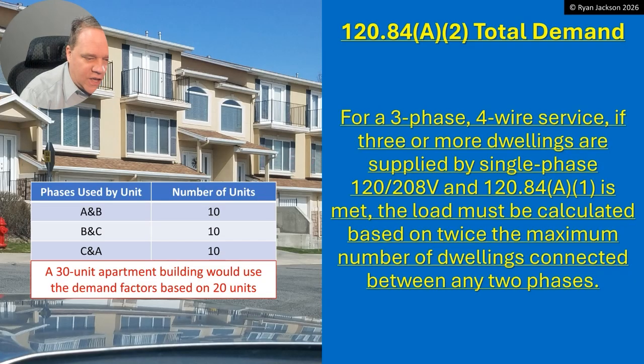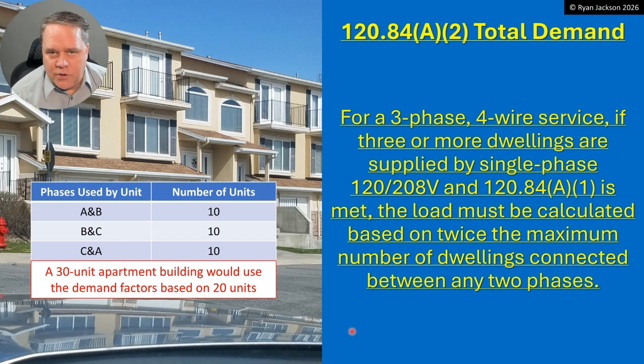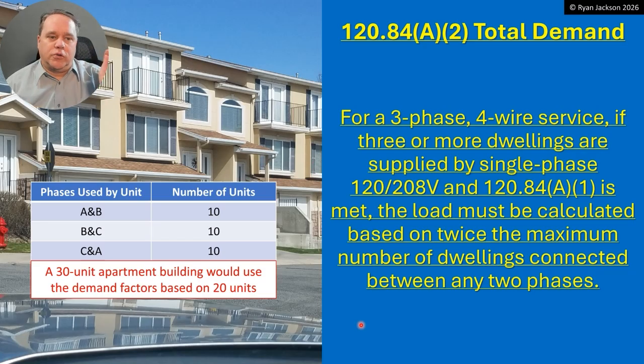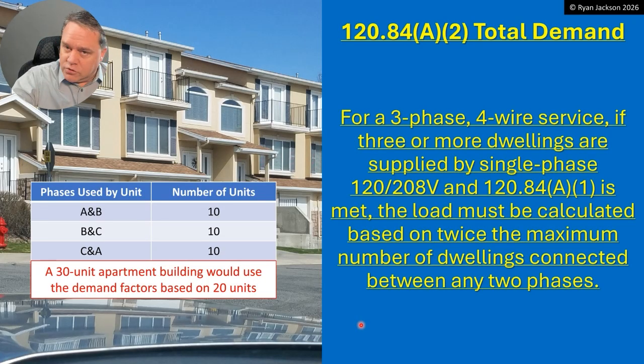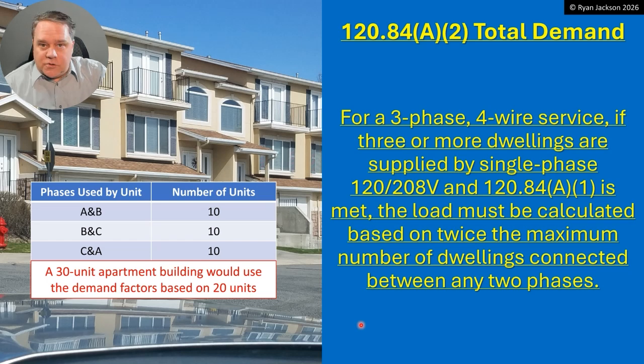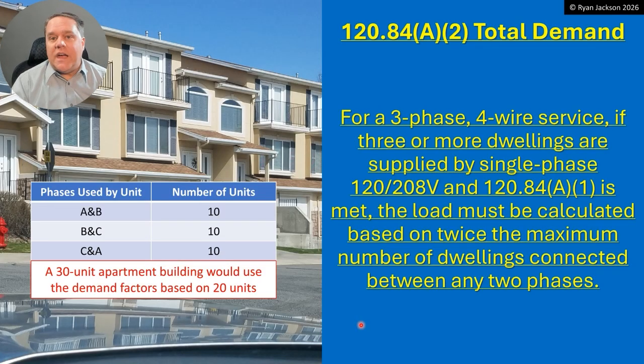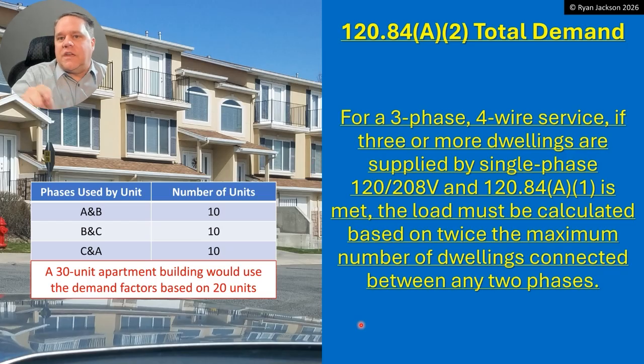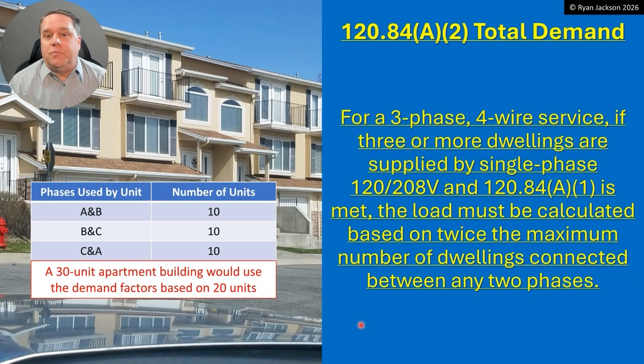Here's the deal: I've got an apartment building with 30 units, but you're not going to calculate the load based on 30 units — you're going to calculate it based on 20. Here's why: you're not going to take phase AB and neutral to all 30 units. You take AB-neutral to some, BC-neutral to others, CA-neutral to the rest, and rinse and repeat. The maximum number of units supplied by phases A and B is 10, B and C is 10, and C and A is 10. So phase A has 20 units on it, phase B has 20, and phase C has 20. No wire in this building is touching all 30 units.